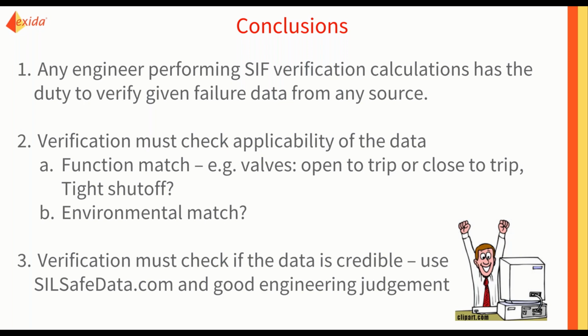I'd like to conclude by reminding all of you that any engineer performing SIF verification calculations has the duty to verify the given data from any source. The verification must check applicability of the data. Is it a functional match? Is it an environmental match? And number 3, the verification must check if the data is credible. Help yourself to SIL-safe data and add in a good dose of engineering judgment.